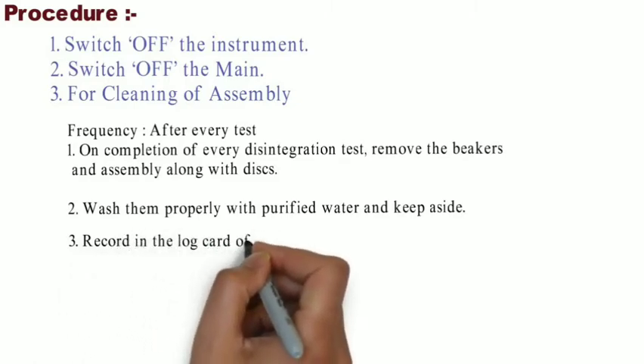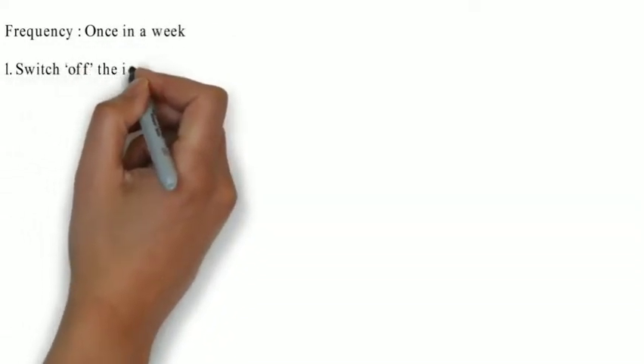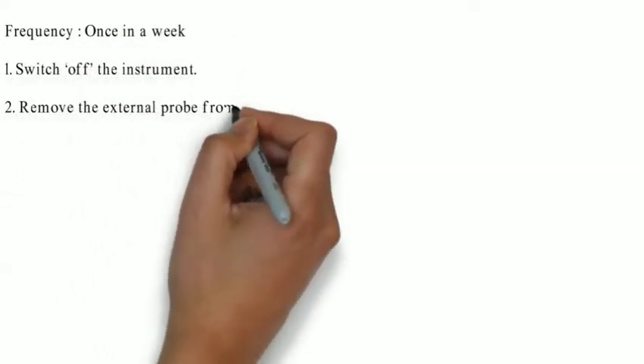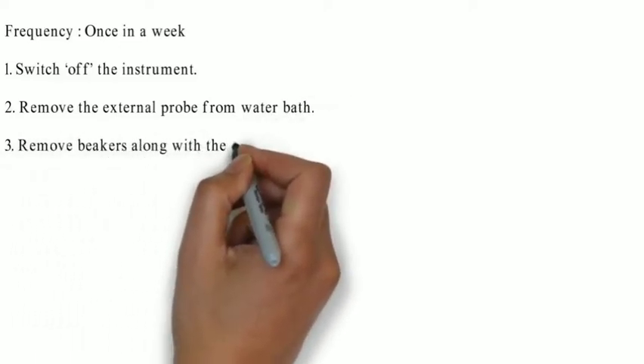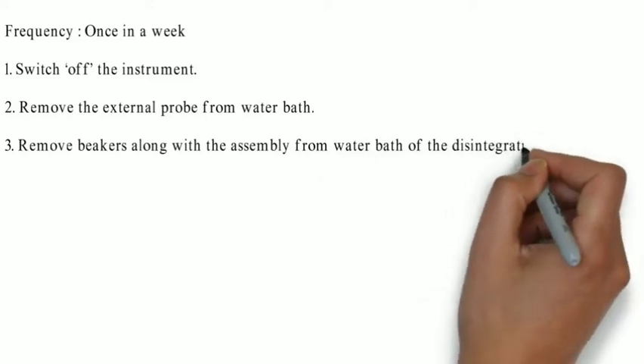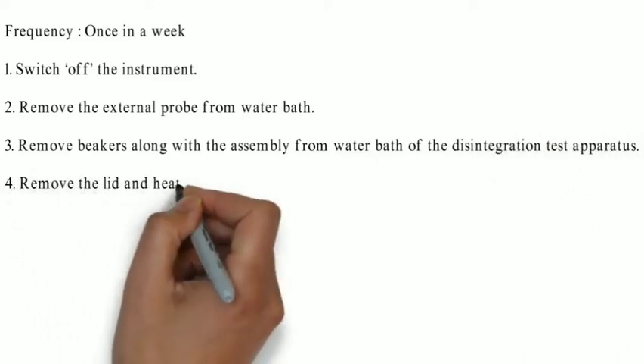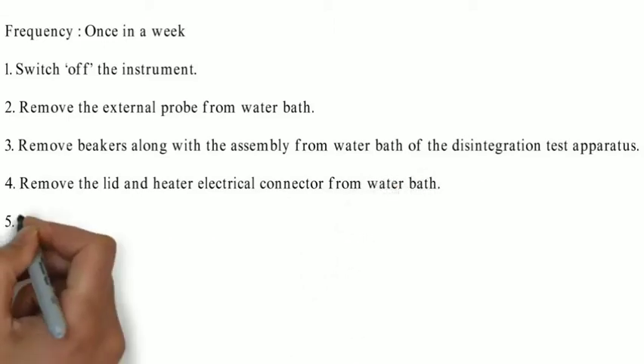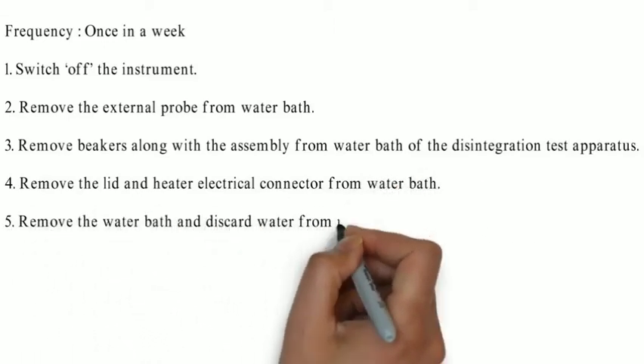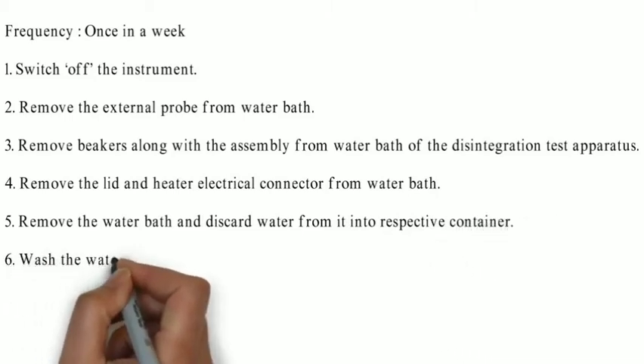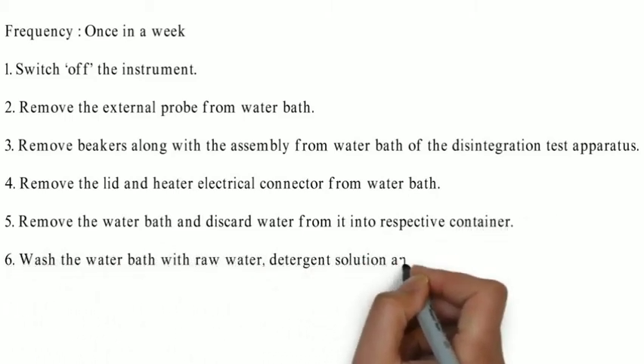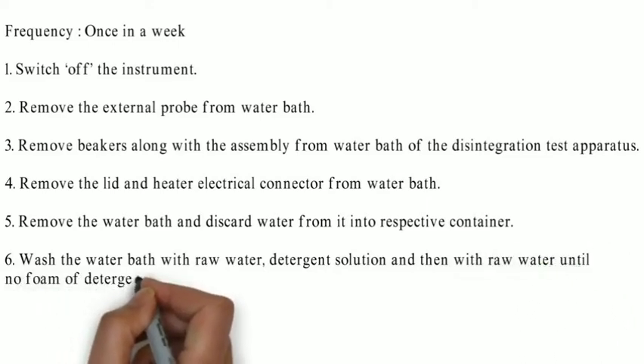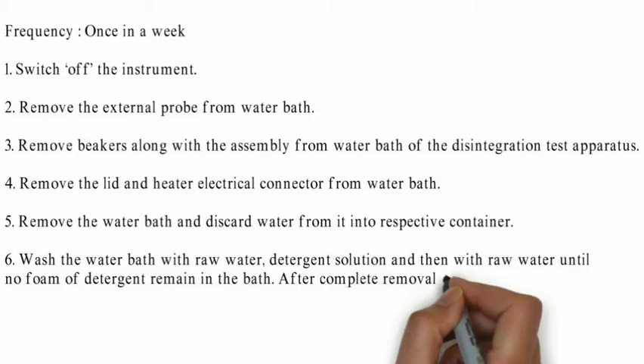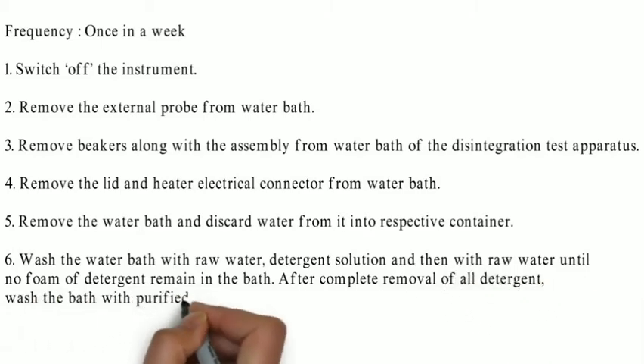Record in the log card of instruments. And for the water bath, frequency: once in a week. Switch off the instruments, remove the external probe from the water bath, remove the beaker along with the assembly from the water bath of the disintegration test apparatus. Remove the lid and heater electrical connector from the water bath. Remove the water bath and discard the water from it into the respective container. Wash the water bath with raw water, detergent solution and then with raw water until no foam of detergent remains in the bath. After complete removal of all detergent, wash the bath with purified water.